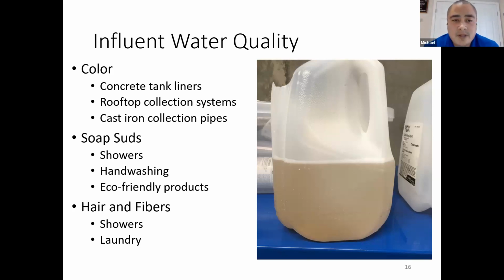The second bullet point: rainwater collection systems. If they're on the rooftop and there's a rainwater collection system, they may have planters on the roof where it runs through the system, giving a high concentration of dissolved solids. Or on the roof, a lot of times there's maintenance happening through the HVAC or whatever it may be, and all of that can come down through our collection pipes that are trying to collect rainwater.